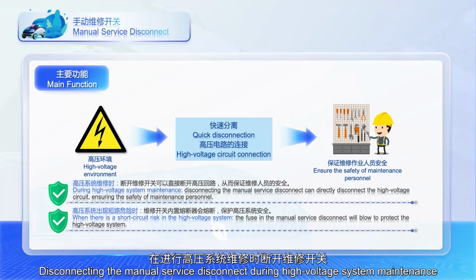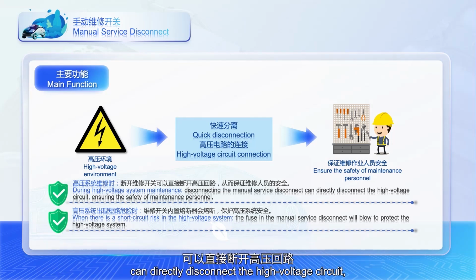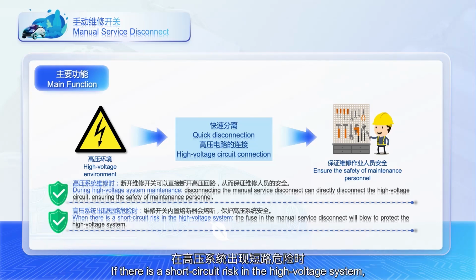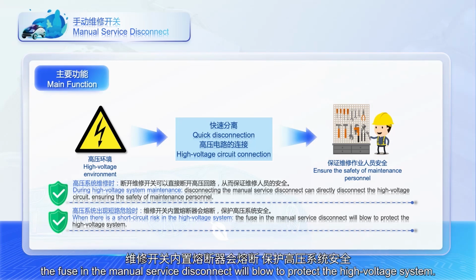Disconnecting the manual service disconnect during high-voltage system maintenance can directly disconnect the high-voltage circuit, ensuring the safety of maintenance personnel. If there is a short-circuit risk in the high-voltage system, the fuse in the manual service disconnect will blow to protect the high-voltage system.